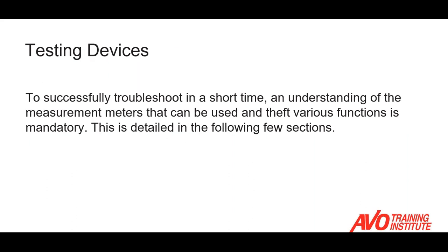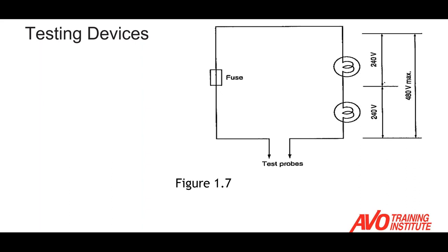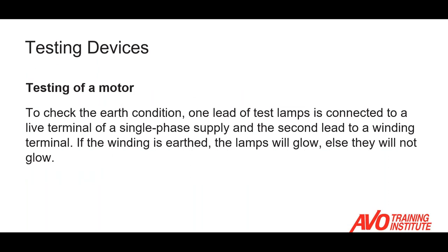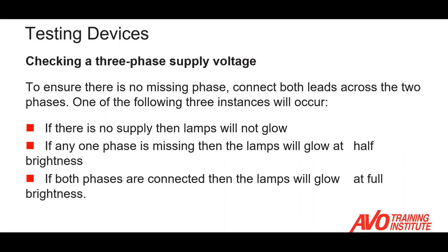To successfully troubleshoot in a short time, you need to understand the measurement meters, different test equipment, and how they can be used. Here we have a lamp indicator — we're using these lamps to check a live circuit; it is fused. If we have a continuous path and a live circuit, the lamps will illuminate. We can use a lamp indicator for several different applications — most commonly, to detect the presence of live voltage. When testing a motor and checking for an earth condition, those lamps can be connected to a winding with a single-phase supply. If the winding is earthed, the lamps will glow; if there's not a path to ground, you won't get any illumination.